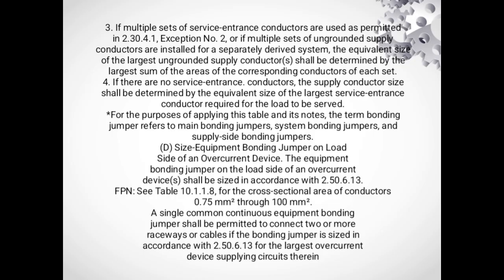D. Size equipment bonding jumpers on load side of an overcurrent device. The equipment bonding jumper on the load side of the overcurrent devices shall be sized in accordance with 2.50.6.13 for a cross-sectional area of conductor 0.75 mm squared through 100 mm squared. A single common continuous equipment bonding jumper shall be permitted to connect two or more raceways or cables if the bonding jumper is sized in accordance with 2.50.6.13 for the largest overcurrent device supplying circuits therein.